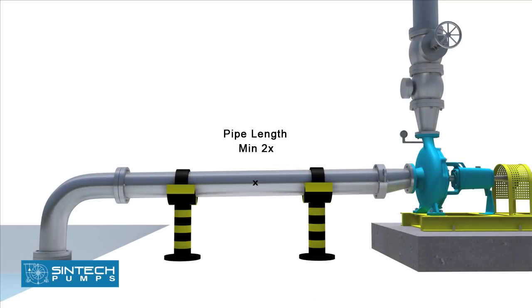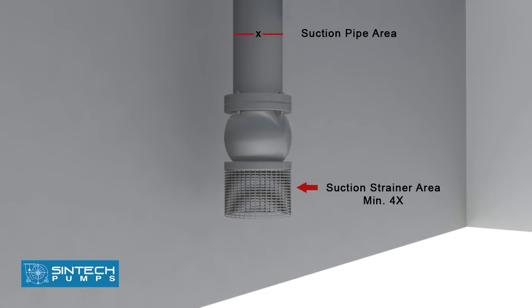The straight length of the pipe after the eccentric reducer should be 2 times the pipe diameter. The suction strainer must be at least 4 times the suction pipe area and the mesh size should screen out solid particles that could clog the impeller.